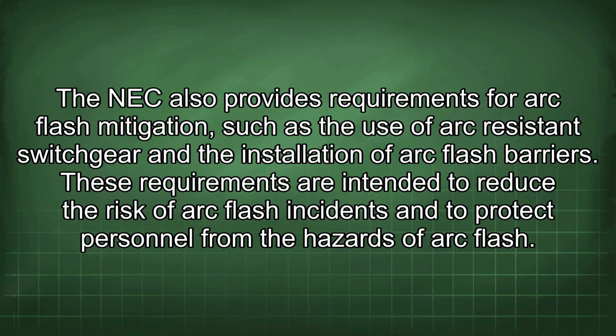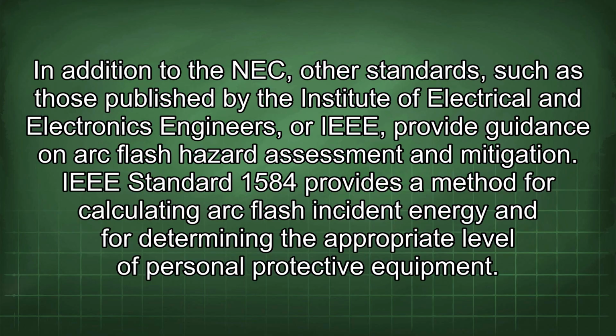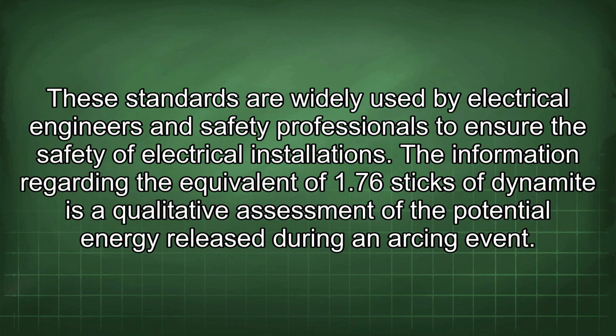These requirements are intended to reduce the risk of arc flash incidents and to protect personnel from the hazards of arc flash. In addition to the NEC, other standards, such as those published by the Institute of Electrical and Electronics Engineers, or IEEE, provide guidance on arc flash hazard assessment and mitigation. IEEE Standard 1584 provides a method for calculating arc flash incident energy and for determining the appropriate level of personal protective equipment. These standards are widely used by electrical engineers and safety professionals to ensure the safety of electrical installations.